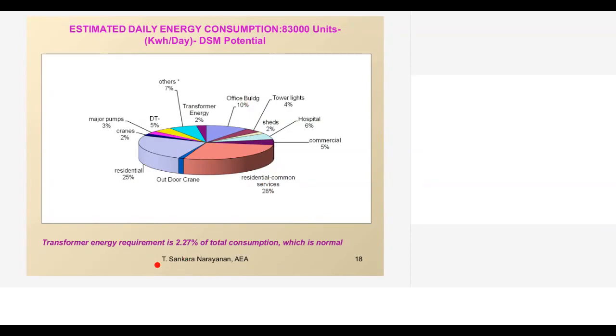Again, here we have made the transformer energy requirement as 2.27, because technically once you are energizing the transformer, we have to provide the energy. But anytime the auditor writes that there is a loss in the transformer, sometimes the reports are read by finance people. They think that all the loss should be controlled. So it is better to give a clarification: this is an energy requirement we have to have. Maybe to some extent I may reduce the I square R loss.